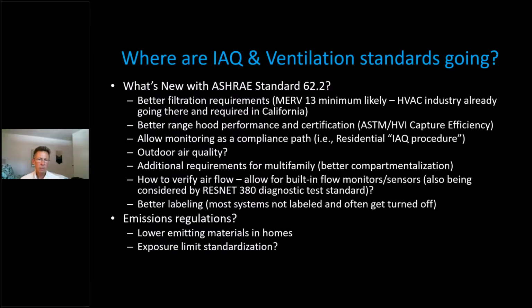which is probably about the right level of filtration for new construction because it's associated with a substantial improvement in health-related filtration, and it can be manageable if designed from the get-go. MERV 13 can cause some pressure drop issues if you put in a MERV 13 filter for a system that wasn't designed for a higher pressure drop, but not all MERV 13 filters end up with a higher pressure drop. So that's a bit of a complicated issue, but I expect it ultimately to lead to higher filtration, higher MERV levels in the standards.